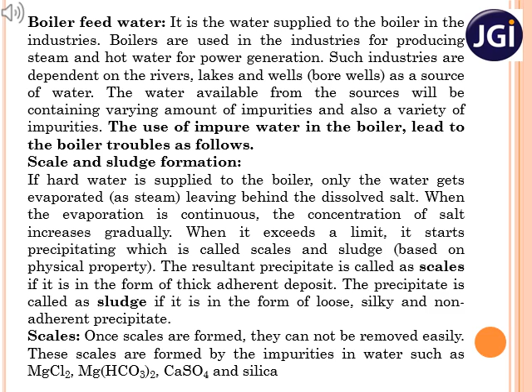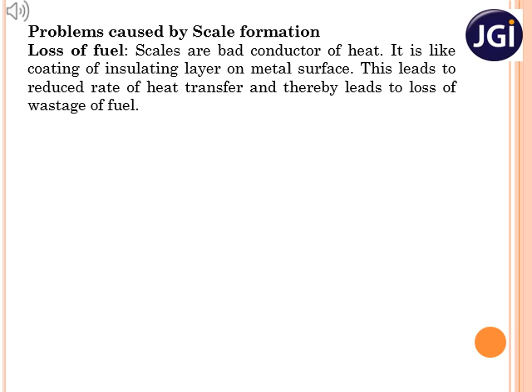The formation of scales leads to reduced heat transfer from boiler to water since scales are bad conductors of heat. Scales form an insulating coating on the metal surface of boiler pipes. This leads to loss of fuel used to heat the boiler water. Excessive scaling leads to the decrease in boiler efficiency.